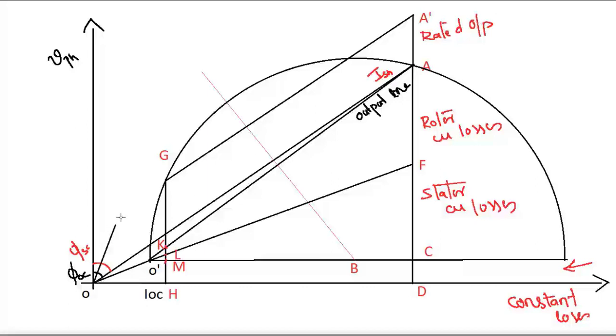From O, draw a line up to G — this is the current drawn by the motor at rated load, and this will be the operating power factor. O'F is called the torque line. With this, the drawing of the circle diagram is almost complete. You can now determine values such as maximum output, maximum torque, maximum input, and maximum power factor using the circle diagram.